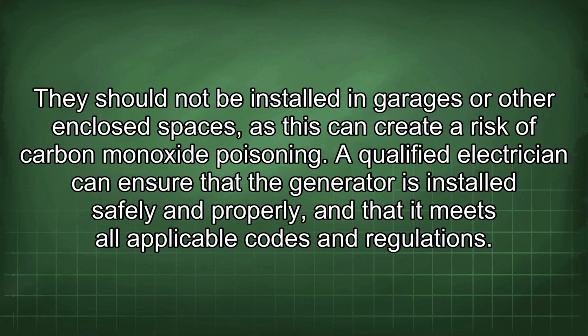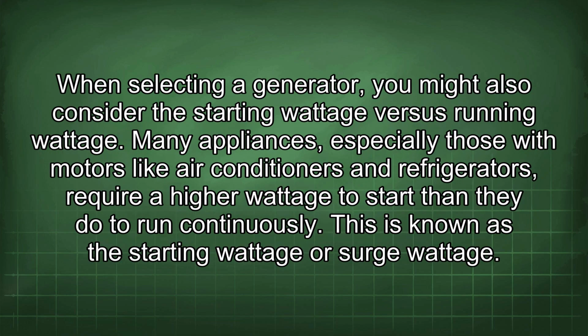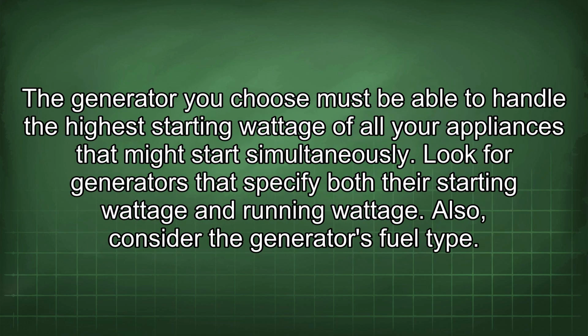codes and regulations. When selecting a generator, you might also consider the starting wattage versus running wattage. Many appliances, especially those with motors like air conditioners and refrigerators, require a higher wattage to start than they do to run continuously. This is known as the starting wattage or surge wattage. The generator you choose must be able to handle the highest starting wattage of all your appliances that might start simultaneously. Look for generators that specify both their starting wattage and running wattage.